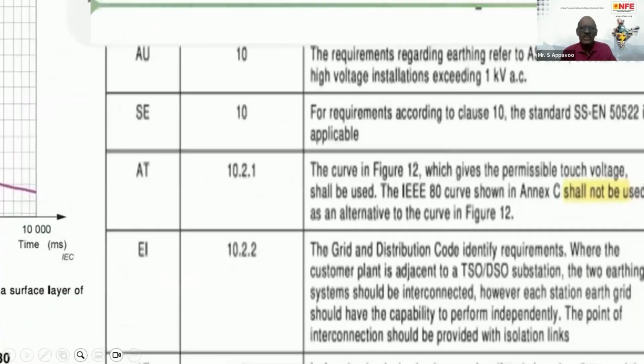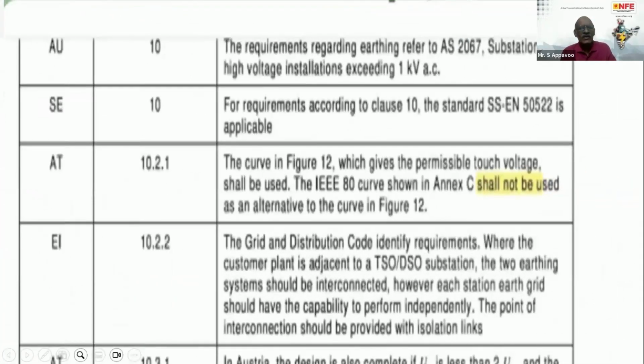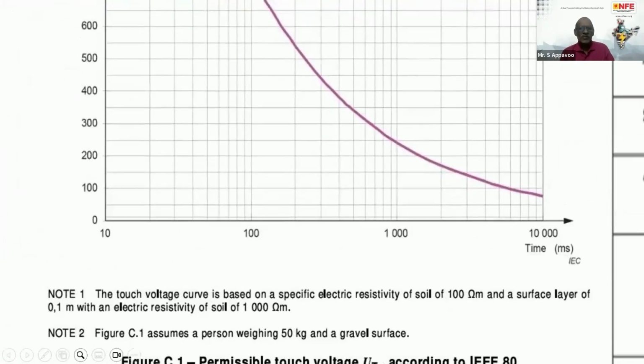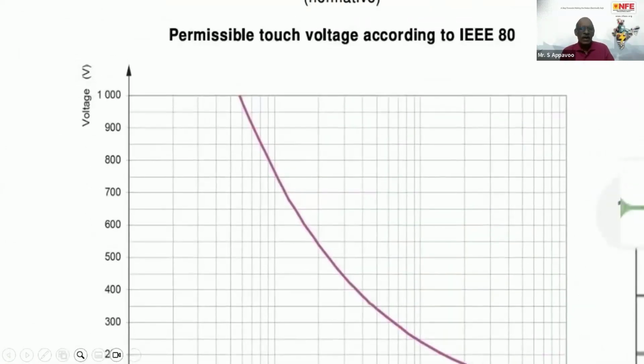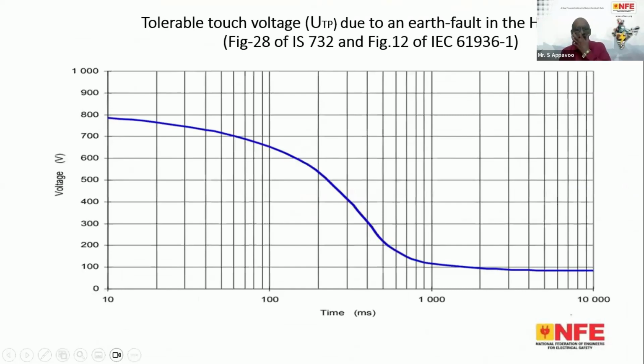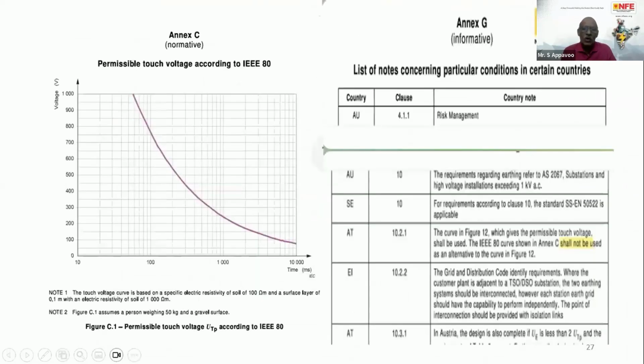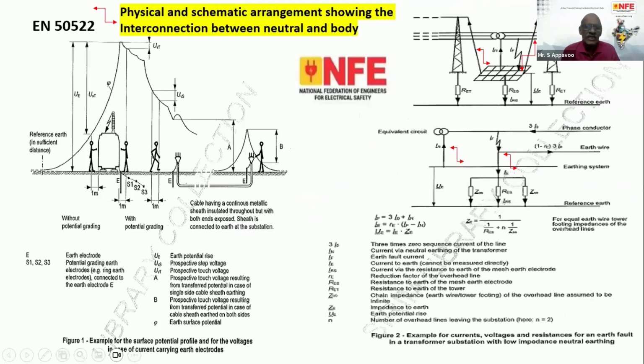curve, figure 12. But for example, you can see that one particular country says the IEC curve in figure 12, which gives the permissible touch voltage, shall be used. That is sufficient. But what they have said is that the IEEE 80 curve shall not be used as an alternative to figure 12. So that means this shall not be used by that country and this shall be used by this country. So these are the things we have to take note of, how the developed world is attempting the reduction of touch potential to minimize the shock hazard to the suppliers' personnel as well as the consumers' personnel.